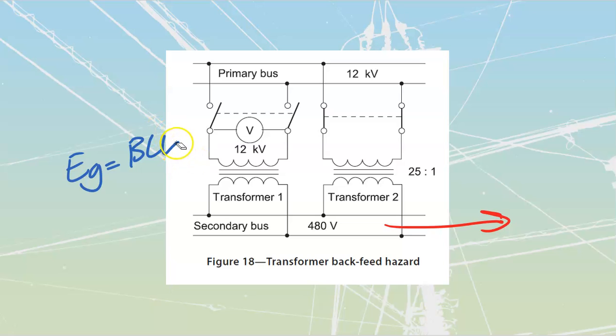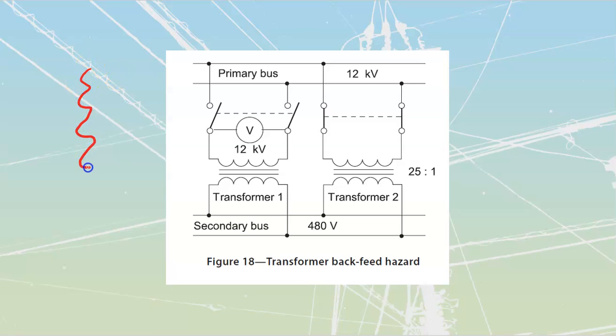However, on paralleled transformers, if there is a chance that you are going to be doing transformer servicing, on a lot of our high voltage systems you have to do periodic servicing because of the bushing. That's the high voltage connection on the top, that ceramic thing. It's got all these rings that are there for drip caps. I'm drawing this thing very poorly, but I think you know what I'm talking about. It's a big white ceramic bushing usually, and then it's going to have a stud on the top, and this is where it's actually going to attach. These are high voltage bushings.